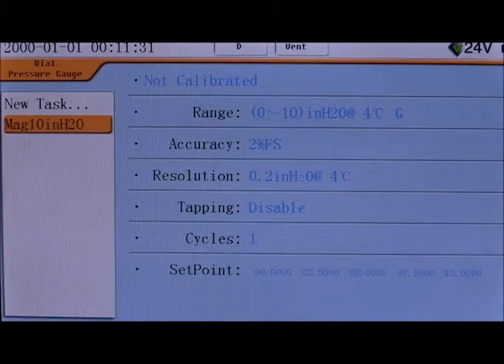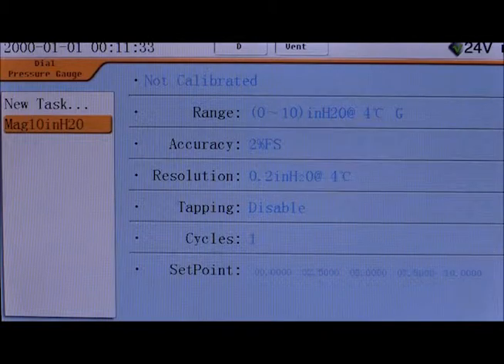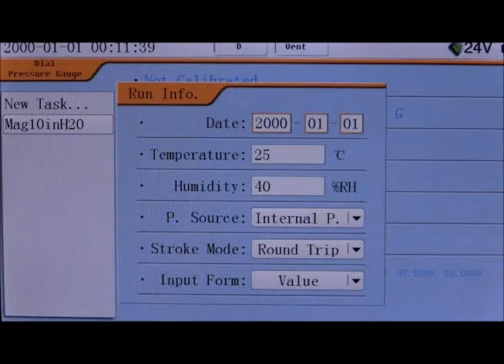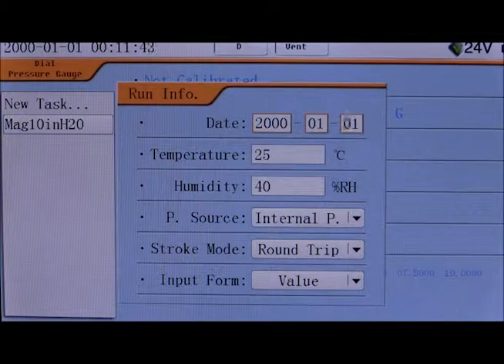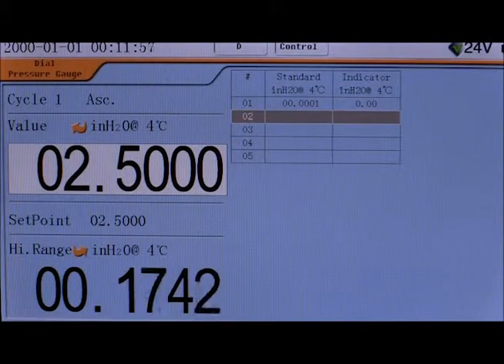With the 761, pre-programmed tasks can be set up and stored in the calibrator's memory. I've created a five-point test with the specifics of this gauge and saved it as a task. I'll select the task and then select Run to start the test. After confirming the environmental conditions and how the test is to run, press Next and the test will begin.